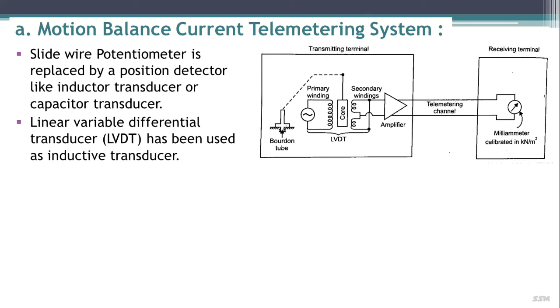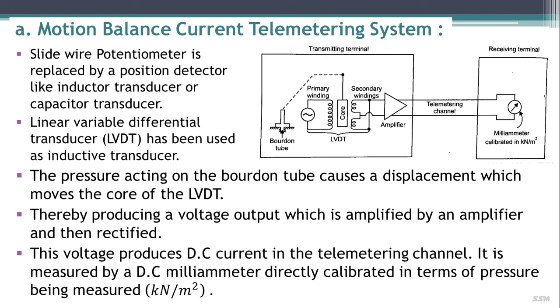The pressure acting on the Bourdon tube causes a displacement which moves the core of the LVDT, thereby producing a voltage output which is amplified by an amplifier and then rectified. This voltage produces DC current in the telemetric channel and is measured by a DC milliammeter directly calibrated in terms of the pressure being measured, that is kilonewton per meter square. The main difference between the newer version and the older version is that the slide wire is replaced by an LVDT.